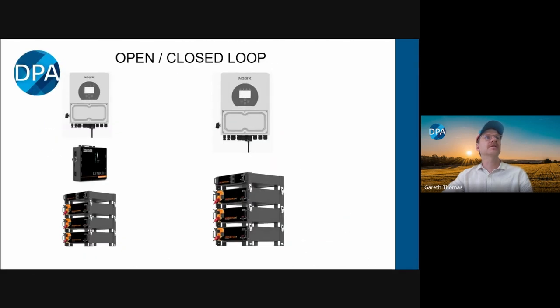So the advantage of these systems is that with many batteries, you can only do closed loop designs, which means if they lose their comms to the inverter, the battery system will stop working. Whereas the Discover systems can be used in open or closed loop, so they can operate independently of communication with the inverter, just like a lead acid bank, like Power Plus can, or they can be in a closed loop design. So you might want to go open loop because you don't want to include the LYNK II because you're on a budget, maybe just have one battery.